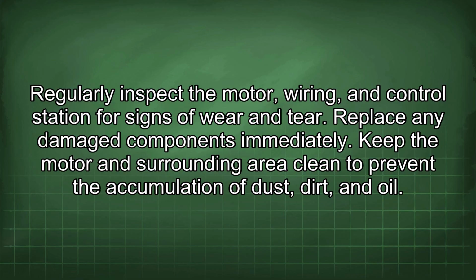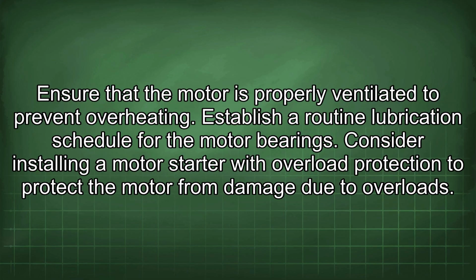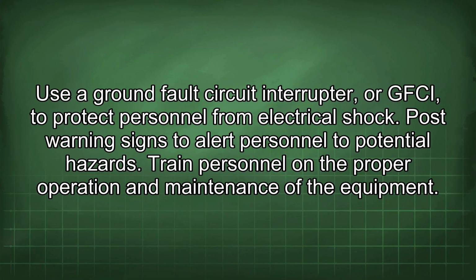Keep the motor and surrounding area clean to prevent the accumulation of dust, dirt, and oil. Ensure that the motor is properly ventilated to prevent overheating. Establish a routine lubrication schedule for the motor bearings. Consider installing a motor starter with overload protection to protect the motor from damage due to overloads. Use a ground fault circuit interrupter, or GFCI, to protect personnel from electrical shock.